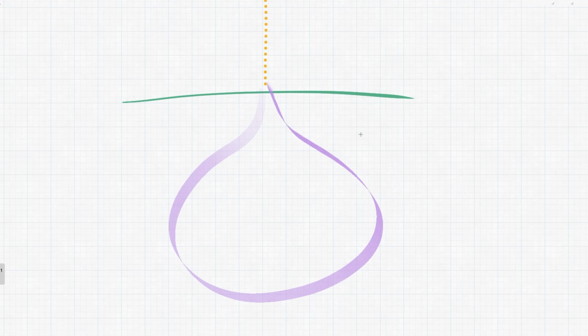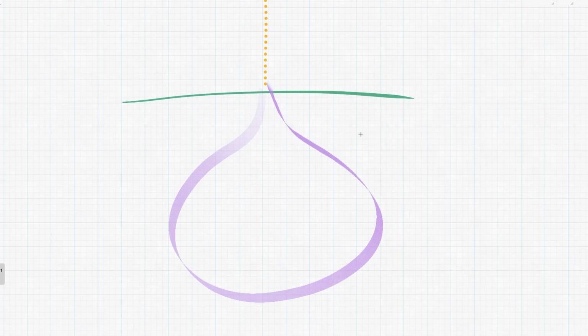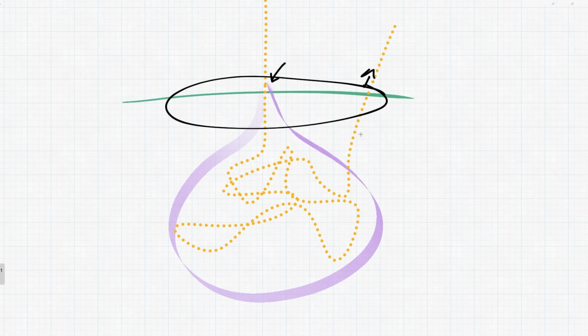The interaction volume depends on the type of event that's happening. So a backscattered electron event might happen relatively deep in the sample, whereas a secondary electron event happens closer to the surface. But in all cases, this distance is relatively small, say 100 nanometers. What's important about this interaction volume is that it blurs the image. It reduces our resolution because the electron might enter and then start bouncing around before being emitted. And you can see that while the electron entered here, it exited over here.